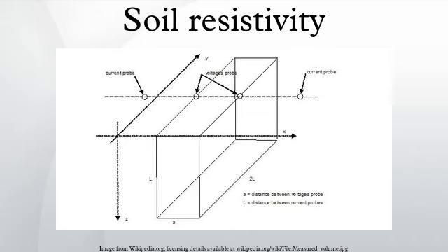Corrosion. Soil resistivity is one of the driving factors determining the corrosiveness of soil. The soil corrosiveness is classified based on soil electrical resistivity by the British standard BS 1377 as follows: greater than 100 Ω·m, slightly corrosive; 50 to less than 100 Ω·m, moderately corrosive; 10 to less than 50 Ω·m, corrosive; less than 10 Ω·m, severe.